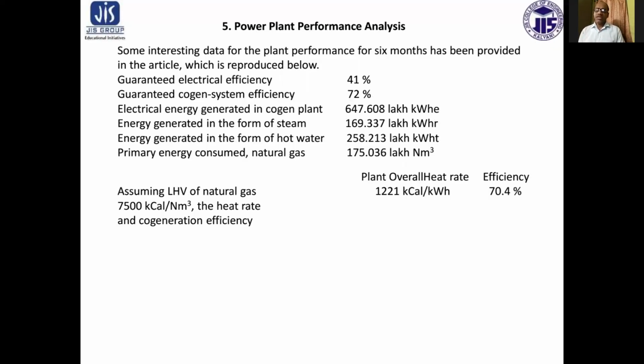Power plant performance analysis. Some interesting data for the plant performance for 6 months has been provided in this article. Guaranteed electrical efficiency is 41%, guaranteed cogeneration system efficiency is 72%. Electrical energy generated in the cogeneration plant is 647.608 lakhs kilowatt hour. Energy generated in the form of steam is 169.337 lakhs kilowatt hour. Energy generated in the form of hot water is 258.213 lakhs kilowatt hour.